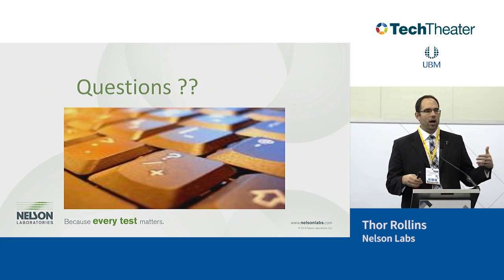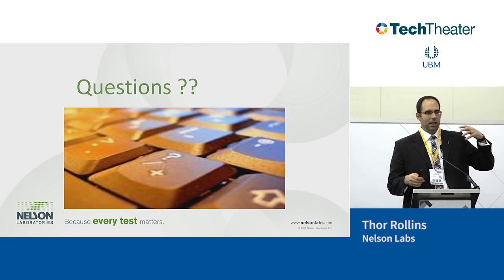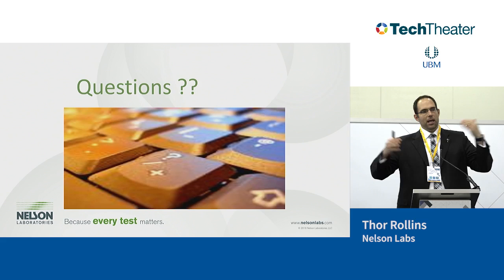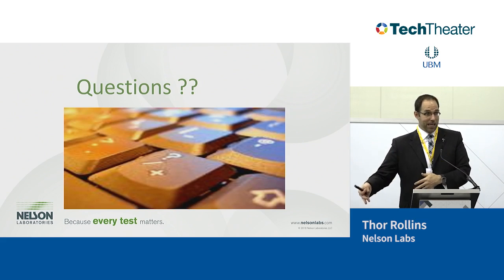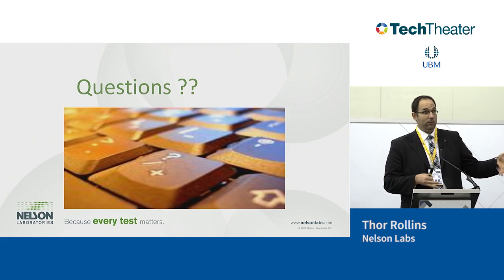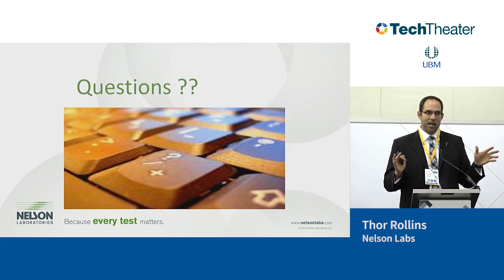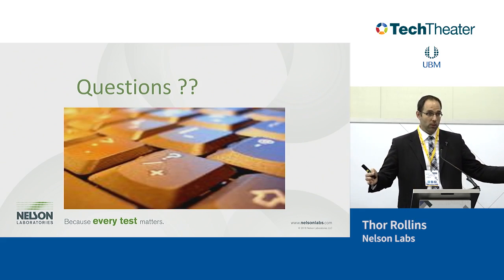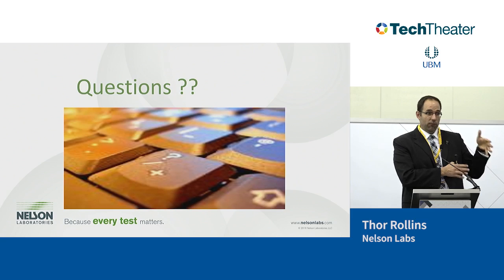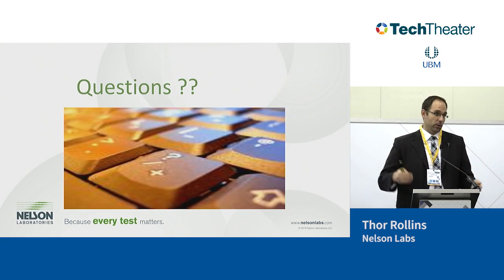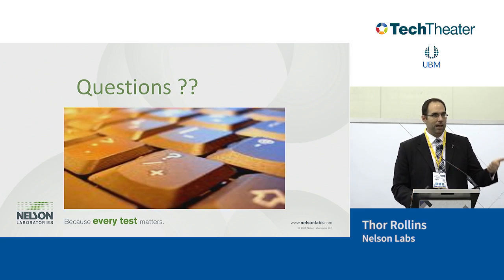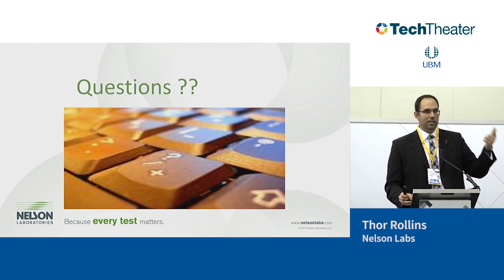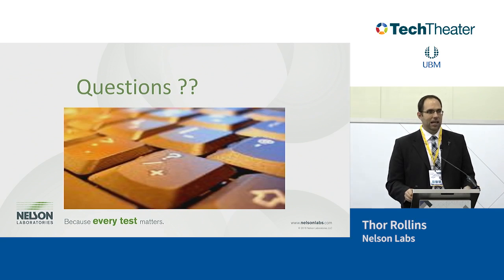And so that's where that upfront work is needed, because if you submit it to the FDA and they evaluate that risk, they're going to have you do the testing, and sometimes those custom tests may take a lot longer to do. So we'd much rather have that risk assessed up front than having to try to respond to an FDA question. But yes, there's a lot of times where the product degrades, for example, or may have a new material or byproduct, something like that, that we may have to assess a different endpoint on this chart than what's in this category.